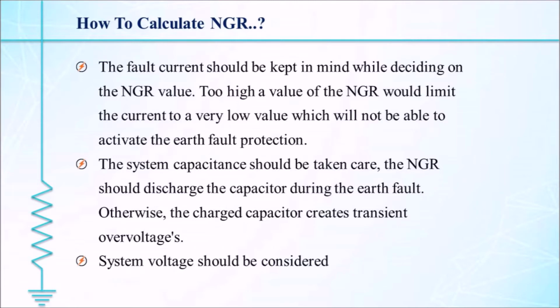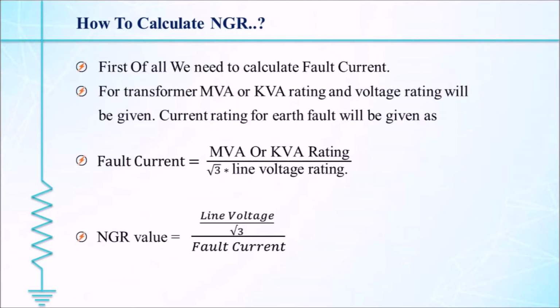Second, the system capacitance should be taken care of. The NGR should discharge the capacitor during the earth fault. Otherwise, the charged capacitor creates transient overvoltages. And third, the system voltage should be considered. This slide gives the formula to find the value of NGR.